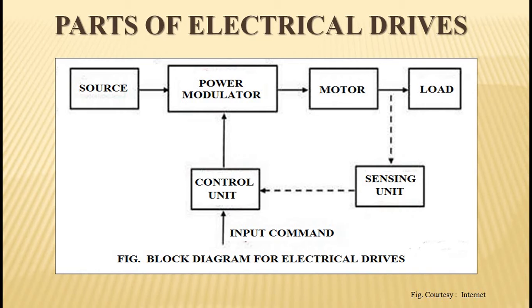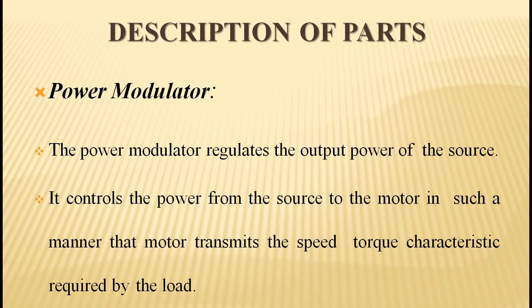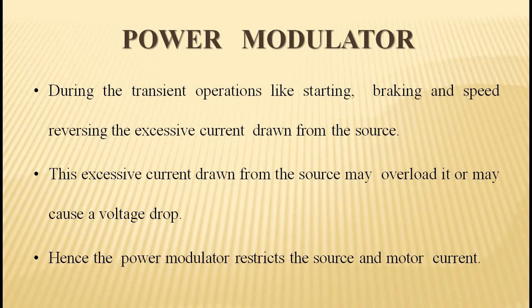Let's go through the important points from this diagram. First, the power modulator. The power modulator regulates the output power of a source. It controls the power from the source to the motor in such a manner that the motor transmits the speed or torque characteristics required by the load. During transient operations like starting, braking, and speed reversing, excessive current may be drawn from the source.